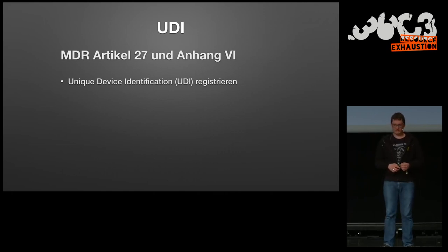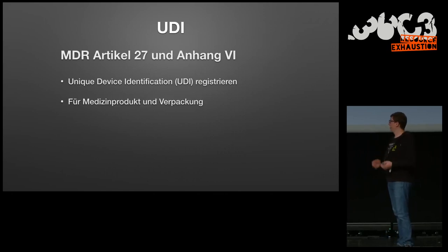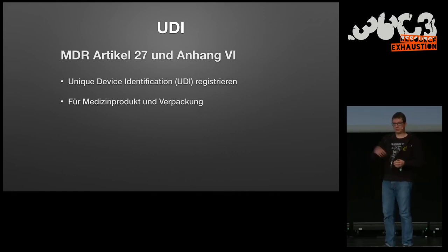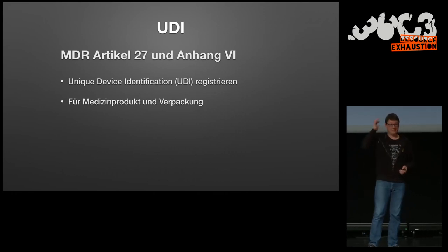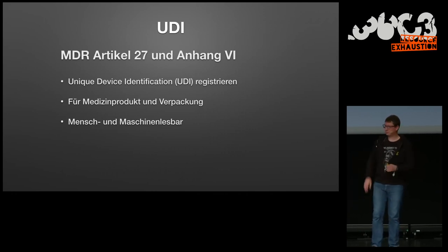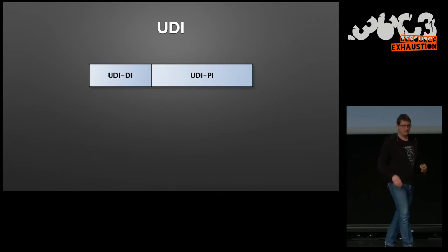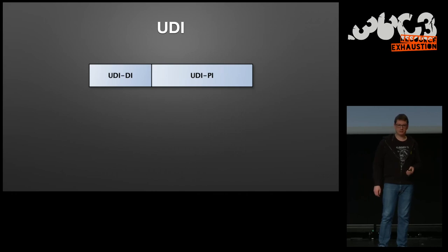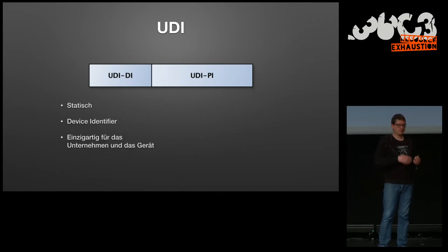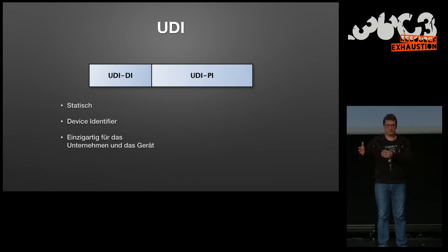So next step, you have to register the UDI, the unique device identifier. It has to be not only on the product but also on the packaging. To talk about this would cost too much time, but I want to talk about it very briefly. There are two parts, the UDI-DI and the UDI-PI. The DI is the static part which identifies the device, the company.